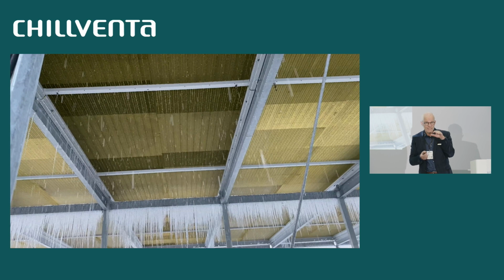While we are defrosting, it's important to keep the hot air inside the coil. How do we do that? Fans are stopped, but we can actually start and stop the fans. If we see that cold air is dropping down, or hot air is flowing up, we can reverse the fan so we keep all the hot air inside. It's very important to remember to keep the hot air inside melting ice instead of just heating air, to have high efficiency during defrost. Small tricks for you when you want to compete against us, or buy a heat pump from us. That's maybe easier.